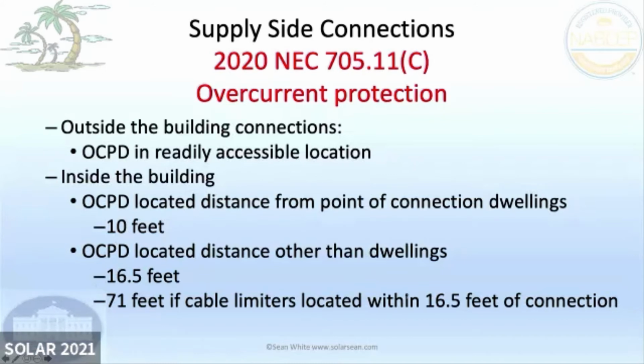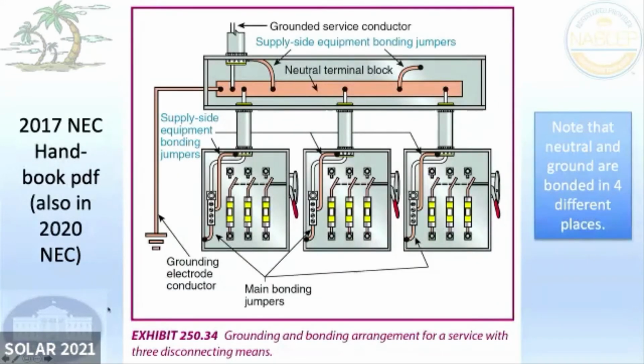Or if you wanted to go further than 16.5 feet, you can put in these things called cable limiters, which are sort of like overcurrent protection, but only for short circuits, for super high currents. Cable limiters. If you've got two wires that cross each other, you want it to open up the circuit and burn up these cable limiters before the whole wire burns. And then you could go 71 feet. I just thought 71, that's kind of a weird number.